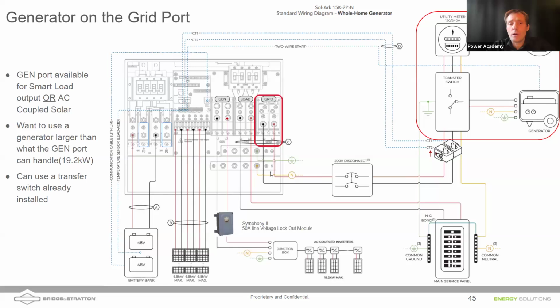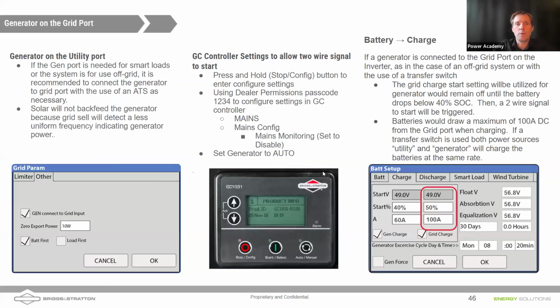So if we additionally have AC coupled solar on that generator port, there are going to be some additional considerations, and you can see that lockout module shown here. We still have the generator on the gen port, so I want you to have these in mind as we go through the settings that we're going to enable here. All right, so first, for a generator on the grid port, the first thing we have to do, under grid parameters, is just let it know, hey, there's a generator connected to the grid input, right?